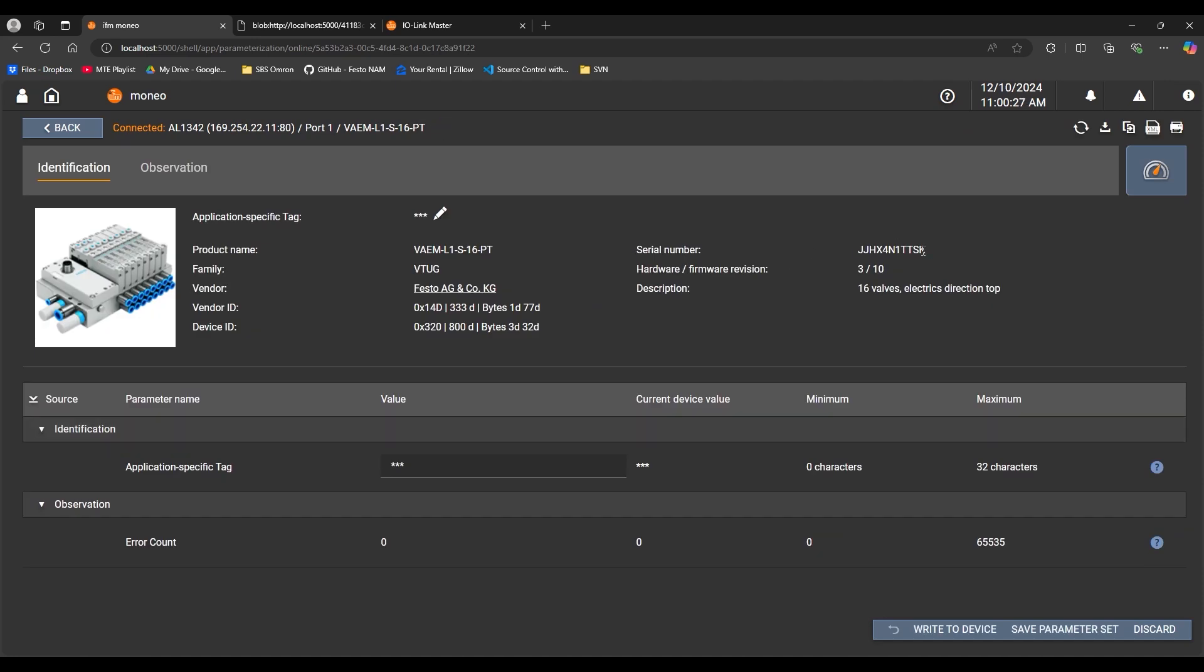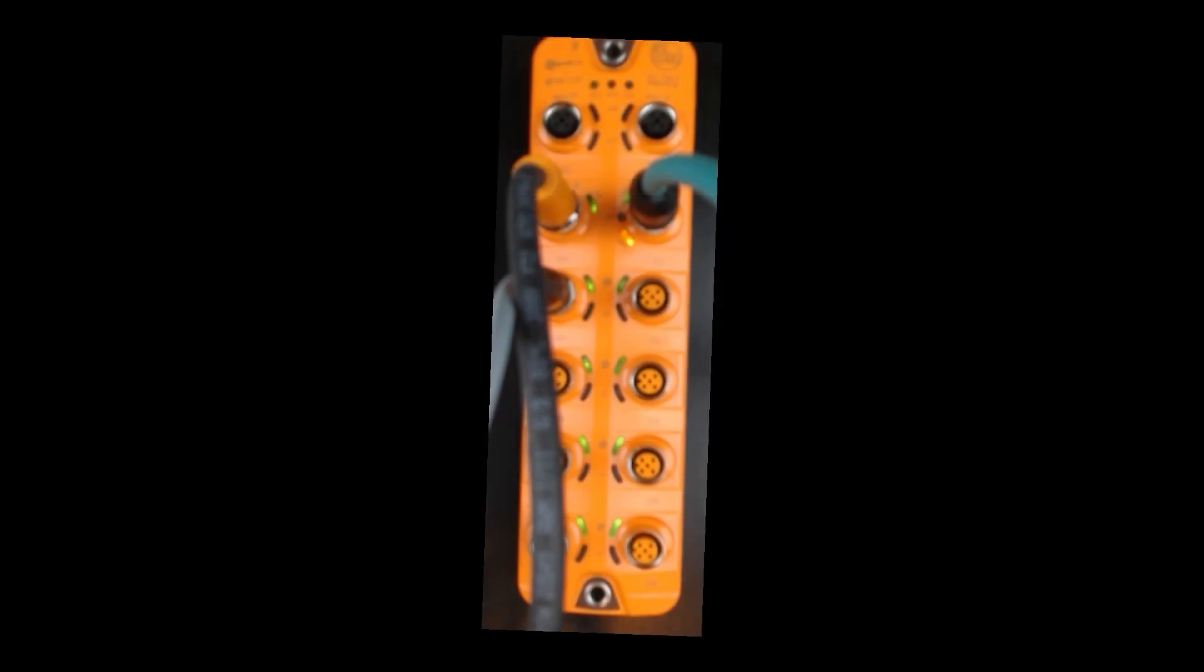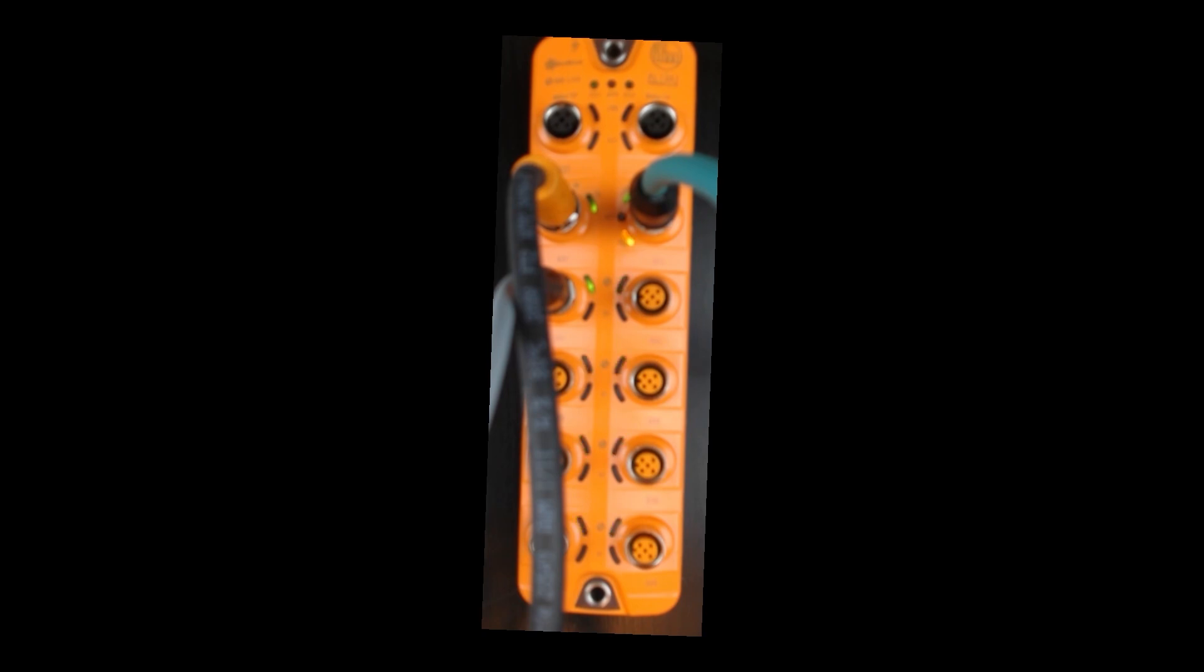I go back to Moneo and actually click on the port one device. You can see that is reflected in my actual value that I now have a different serial number, but an identical part plugged in for this application. And one final thing we want to check, if we go back to our side camera here, we can see that the LED on the port one IO-Link device port is solid green indicating that everything is happy and communicating.